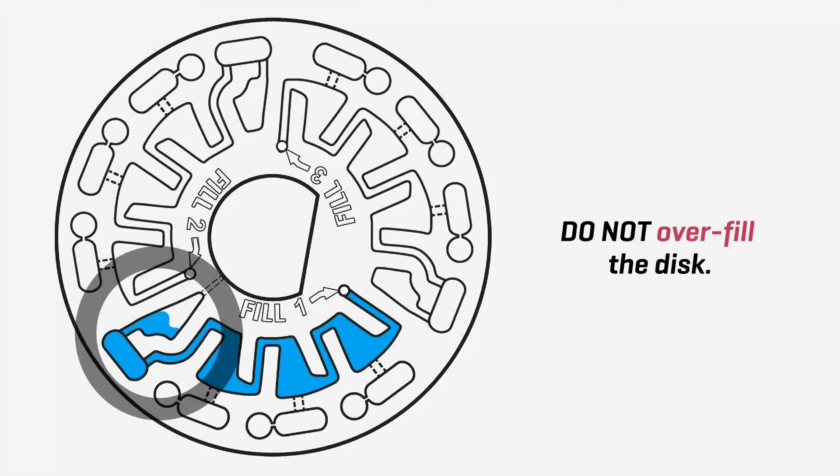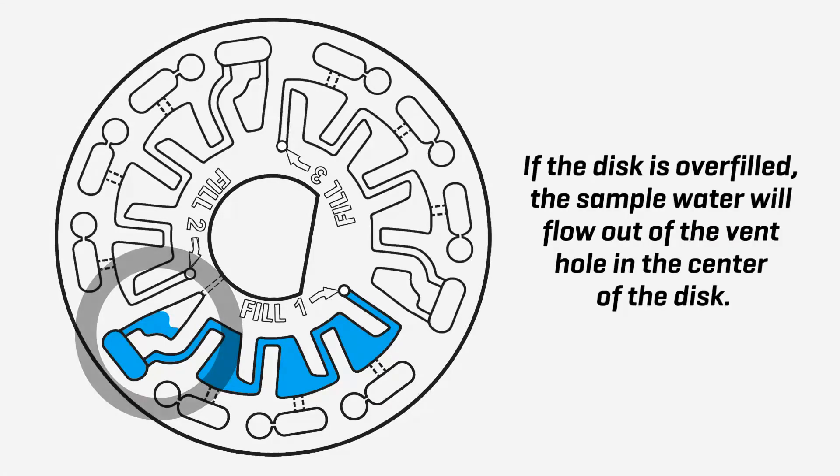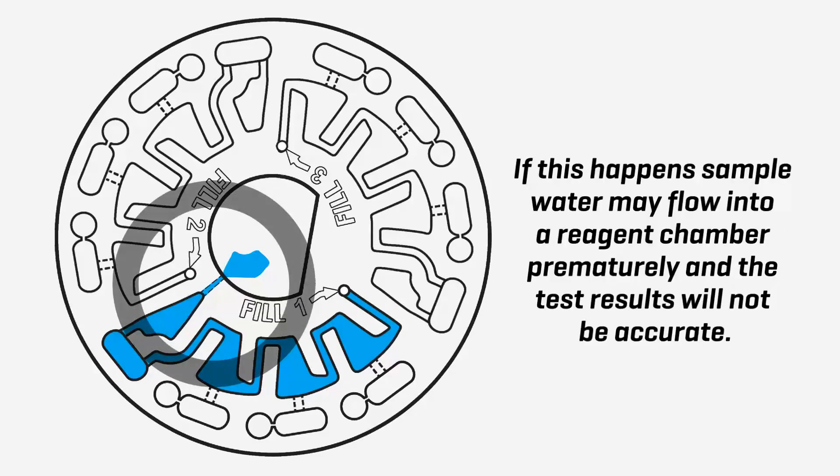Do not overfill the disc. If the disc is overfilled, the sample water will flow out of the vent hole in the center of the disc. If this happens, sample water may flow into the reagent chamber prematurely and the test results will not be accurate.